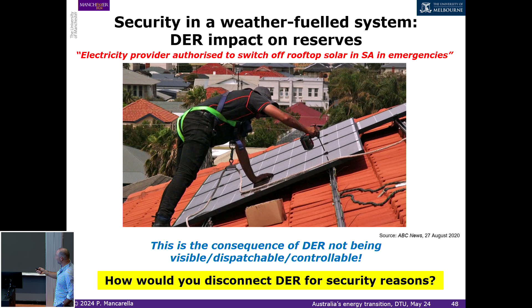And then the very smart people would just start operating the grid with very high voltages—change the tap in the primary substation, operate the grid with very high voltages for a couple of days. You just run with these high voltages, and the rooftop PVs disconnect because of high voltage protection, and then you run the grid with conventional generators. Very smart, of course very inefficient, but this is really what we could do.